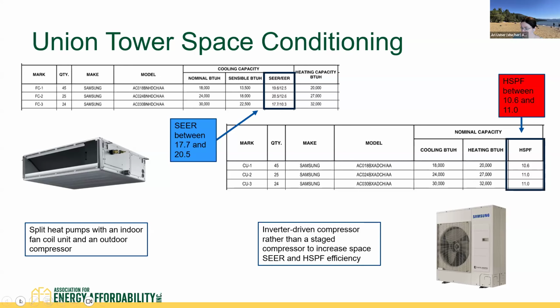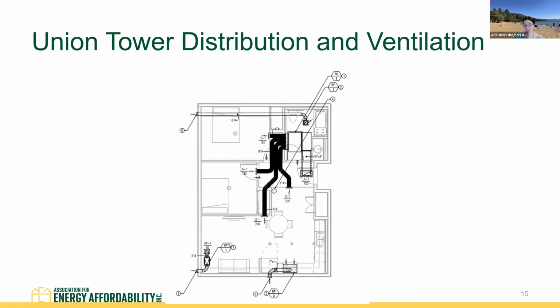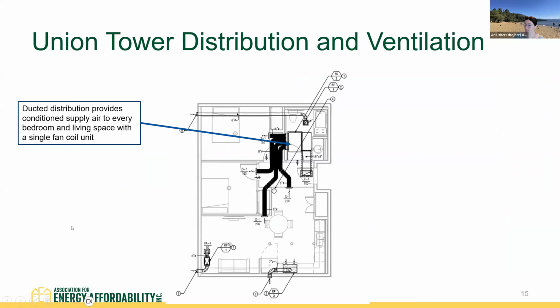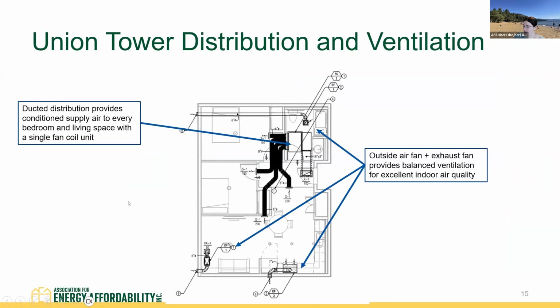So let's talk a little bit about distribution and ventilation. We have HVAC, which is heating, ventilation, and air conditioning. It's not just space conditioning. What we're seeing here on this Union Tower unit plan is ducted distribution, which is providing conditioned supply air to every bedroom and living space with a single fan coil unit. And then we've got our ventilation, including an outside air fan, bringing fresh air in, and 2 exhaust fans. This is what we call balanced ventilation, and it's going to provide for excellent indoor air quality.